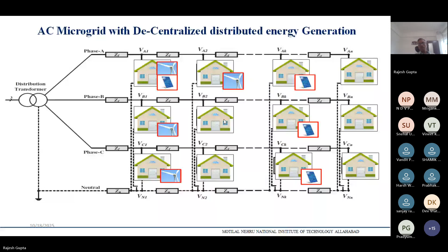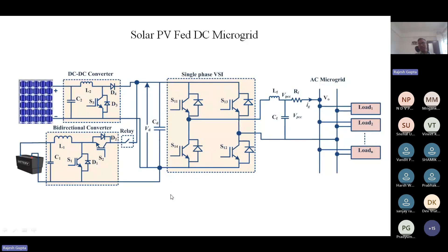Now we can talk a little bit about the DC microgrid. A DC microgrid could look like this. If I say a single phase DC microgrid, this could be a scenario. You have a solar plant with a DC-DC converter. You have a common bus, where the solar plant and your bidirectional converter can be connected. This bus can act as a DC bus, and then if you have AC loads, you can connect the AC loads through another inverter. So that's the kind of scenario possible.